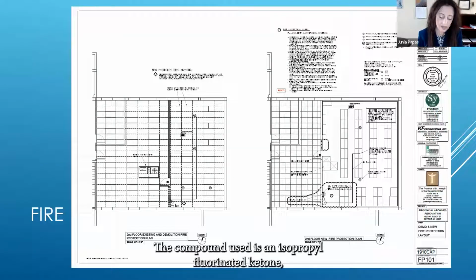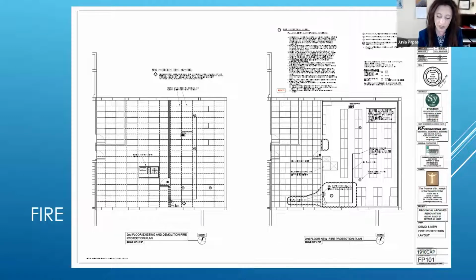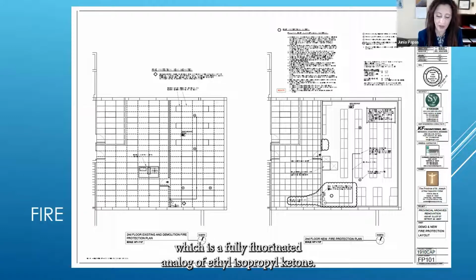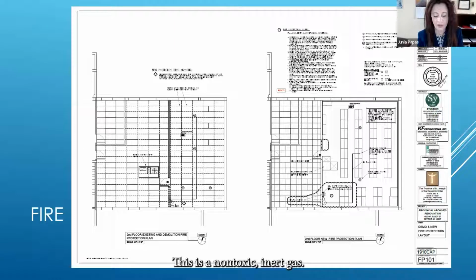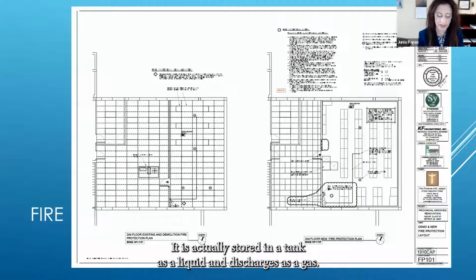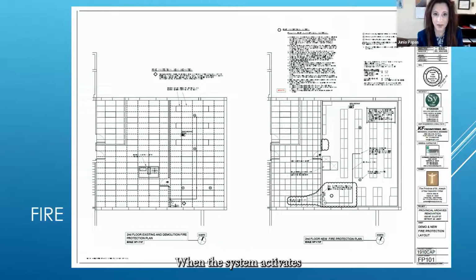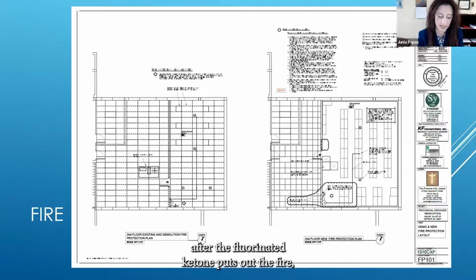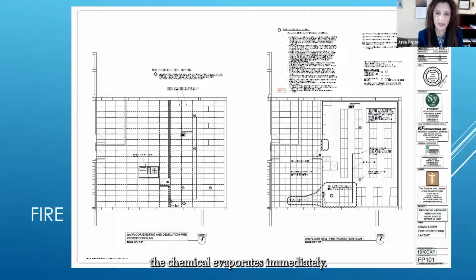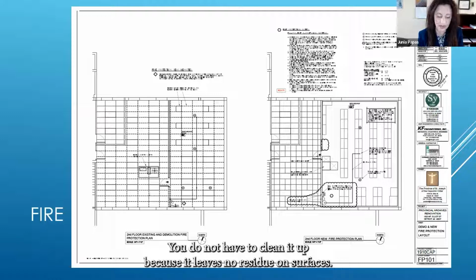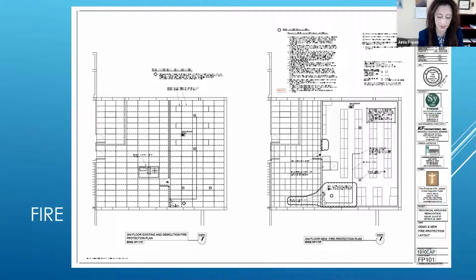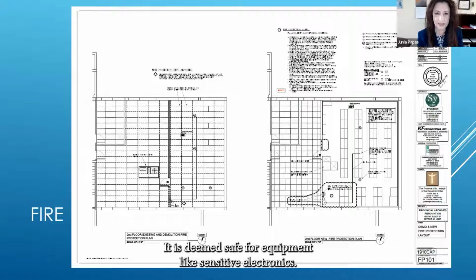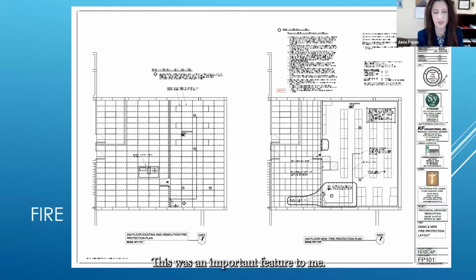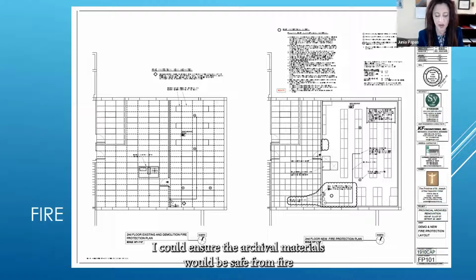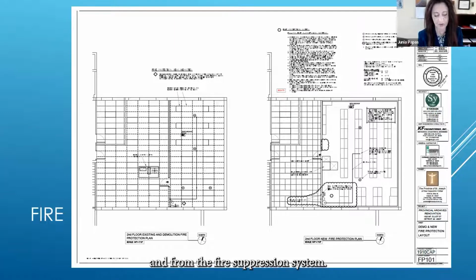The compound used is an ethyl isopropyl fluorinated ketone, which is a fully fluorinated analog of ethyl isopropyl ketone. This is a non-toxic inert gas. It is actually stored in a tank as a liquid and discharges as a gas when the system activates. After the fluorinated ketone puts out the fire, the chemical evaporates immediately. You do not have to clean it up because it leaves no residue on surfaces. It is deemed safe for equipment like sensitive electronics. This was an important feature to me because I could ensure the archival materials would be safe from fire and from the fire suppression system.